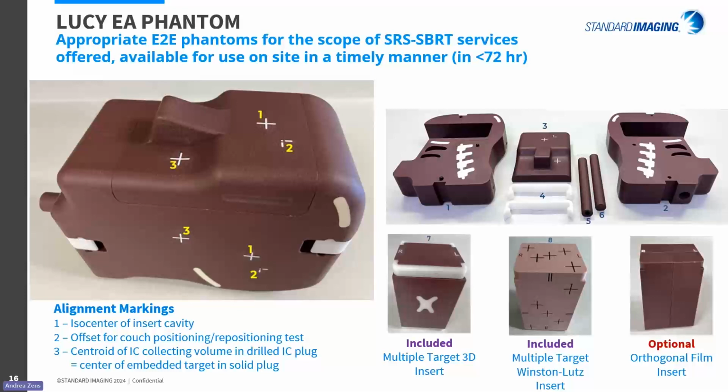The Phantom allows verification of treatment planning software calculations for volume measurements, distance measurements, and image transfer. Dosimetry verification is accomplished via components that accommodate ion chambers or other detectors and film.